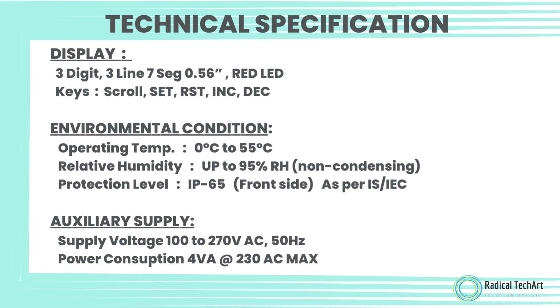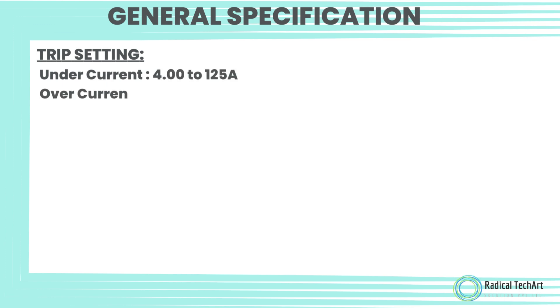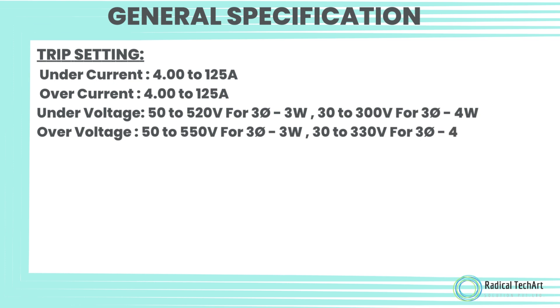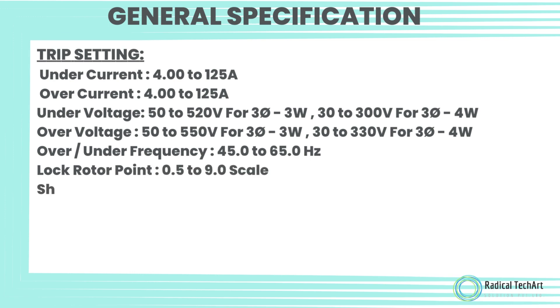Auxiliary Supply — Supply voltage: 100 to 270 Volt AC, 50 Hz; Power consumption: 4 VA at 230 Volt AC max. Trip Settings — Under current: 4 to 125 A; Over current: 4 to 125 A; Under voltage: 50–520 V (3-phase 3-wire), 30–300 V (3-phase 4-wire); Over voltage: 50–550 V (3-phase 3-wire), 30–330 V (3-phase 4-wire); Over/Under frequency: 45–65 Hz; Lock rotor point: 0.5 to 9 scale; Short circuit: 1 to 9 scale; Unbalance: 5 to 60 percent.